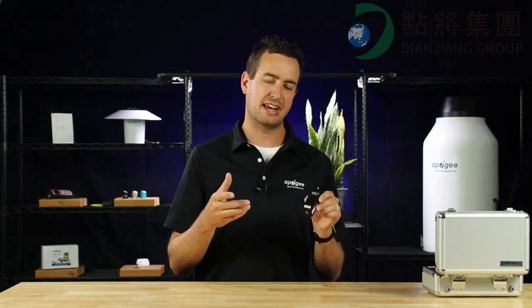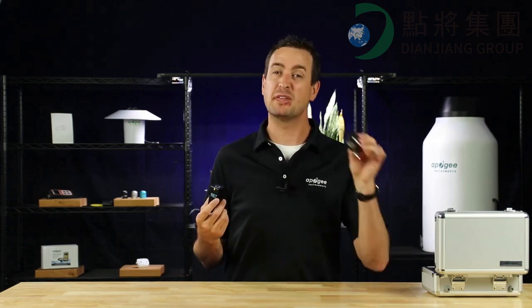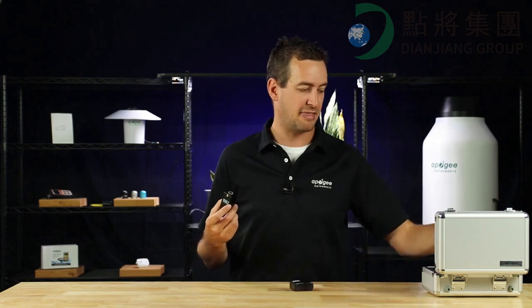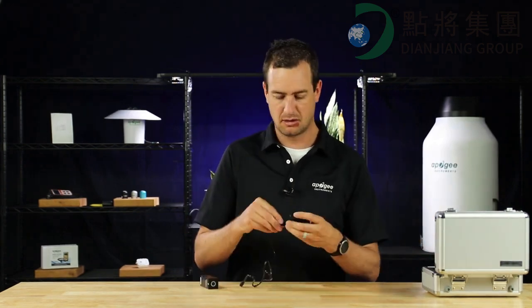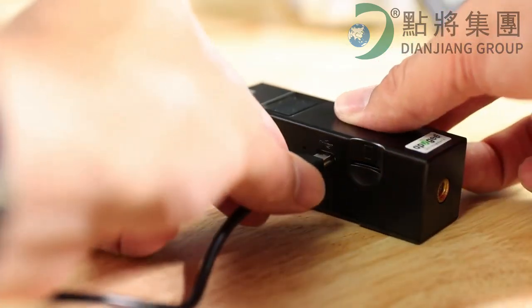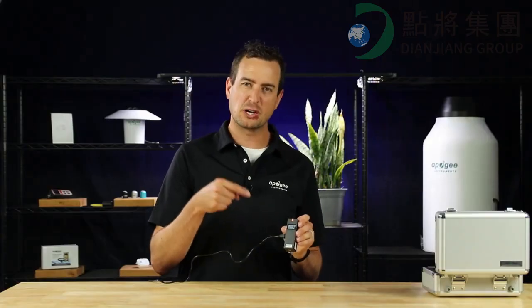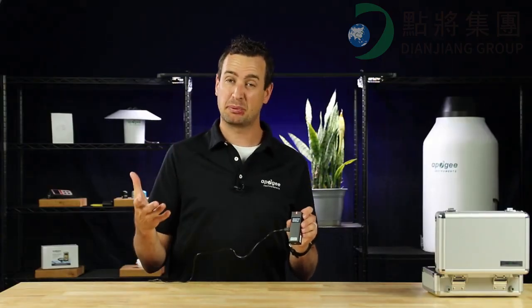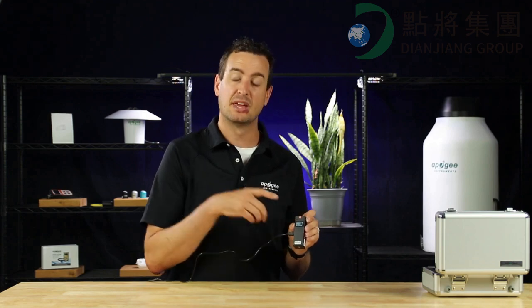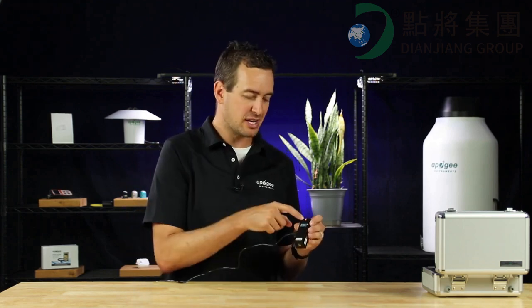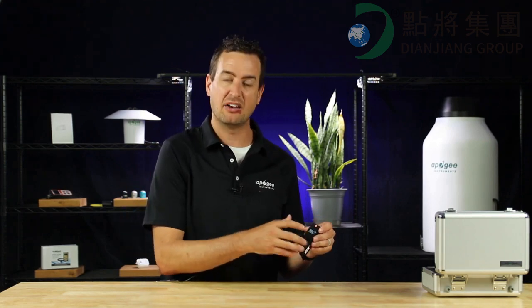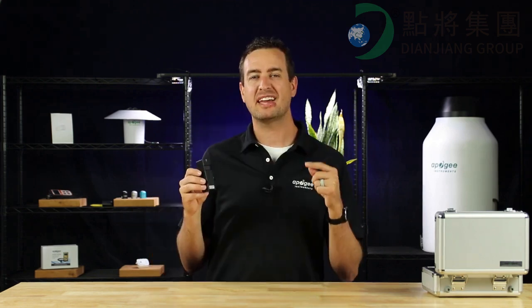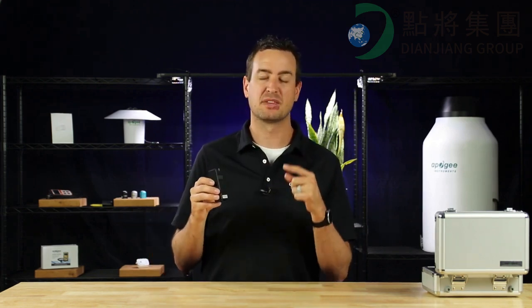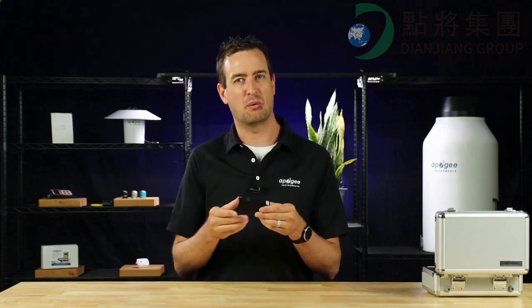Make sure that before the first use of the Insight that you charge the device for at least 6 hours. So grab the USB power adapter and the charging data cable, hook them up, plug it into the Insight. The indicator will turn orange when it's charging. When it's completed charging, it'll turn green. You can tell it's charging either by the orange indicator light or by the icon with the lightning bolt through it. The Insight is intended for lab and field use. As a result, the device is not waterproof, so make sure you don't put it in the water.